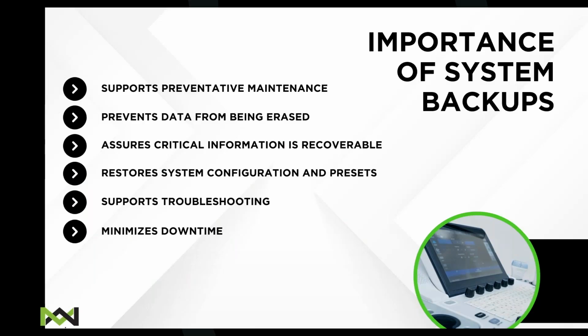Some of the things, this supports preventive maintenance. Part of what I make sure our techs do is every time we're doing a PM on the system, I want them going in and making sure that the first thing they do is create a backup. Like I said, it prevents data from being erased, assures that critical information is recoverable, restores system configuration and presets, supports troubleshooting, and helps minimize our downtime if we're going to do a repair, or if we have to reload system software, or the hard drives are having an issue. We want to make sure we can get the system back up as quickly as possible.